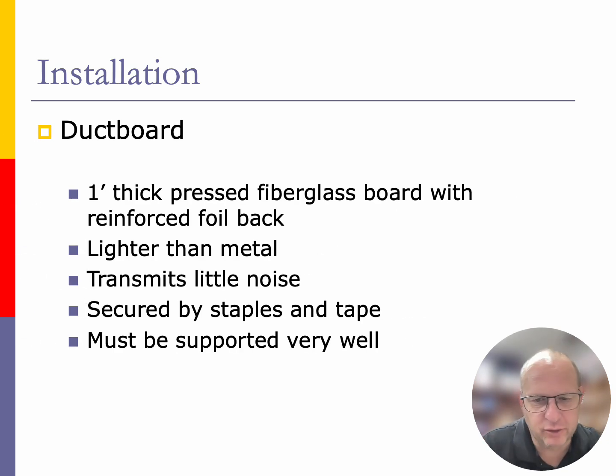So another type of insulation ductwork that's out there for us to install, it's called ductboard. I am not a big fan of ductboard, but it does save time in insulating. It does save time in actually installation of the unit itself. So what is it made of? It's actually made of insulation that's pressed together, fiberglass board with a reinforced vapor barrier foil back on the ductwork itself. It is lighter than metal. It helps cut down on the transmission of noise because of the dampening of the insulation that the ductboard's made of.